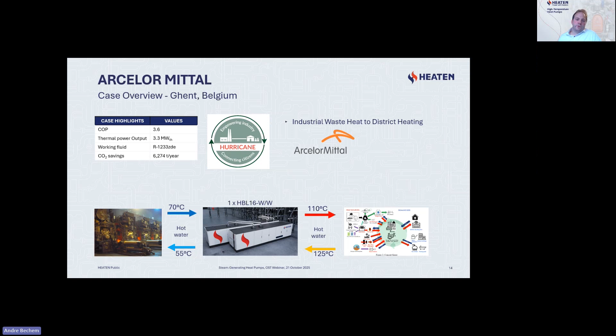This temperature lift is quite big, and admittedly the working fluid here is an HFO. Actually, from a power performance standpoint, it would be better to use isobutane, because that would also enable more power output. In this particular case, though, the customer didn't need more and definitely wanted a non-flammable working fluid, an HFO. That was the decision taken. But of course we could also use isobutane here, and then we would reach a thermal power output of around 6 to 7 megawatts with a single HBL16 machine.